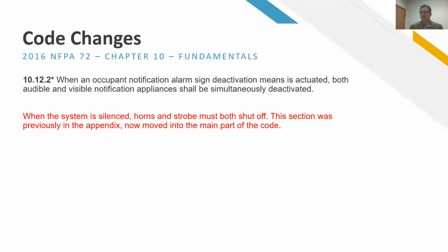Sometimes this becomes an issue on existing systems where the authority having jurisdiction still wants it the old way, and it can be a little bit costly to have it behave this way depending on how things are wired - if you want to kill the horns but keep the strobes, that kind of thing. But if the authority having jurisdiction is requiring that, it's a little bit of leverage to say, well, no, we're in compliance - if we're killing the horns and the strobes, we're in compliance because of this code section right here in front of you.